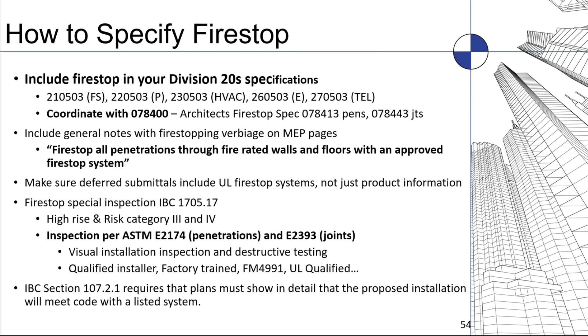But if you do not have a standard to go by, these are still the best standards out there. They are the most reliable types of standards, and that is what is taught to most Firestop inspectors and building inspectors. So even if you don't have a risk category 3 or 4 structure, the best guideline is still to use ASTM E2174 for penetrations and ASTM E2393 for joints. If you put that in your specifications, somebody's going to have a really excellent guideline to walk through your structure and do a really good Firestop inspection.